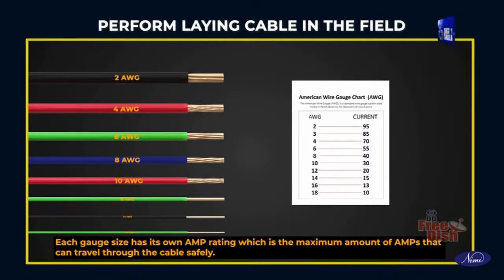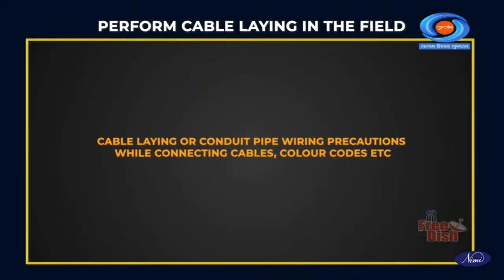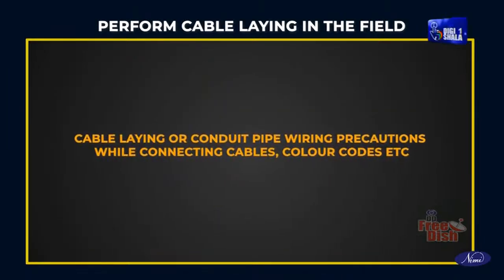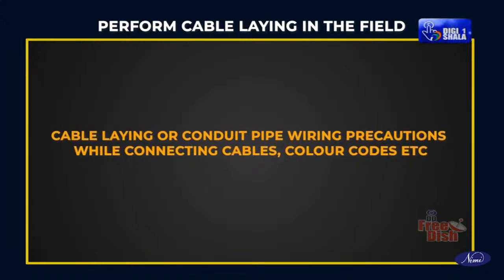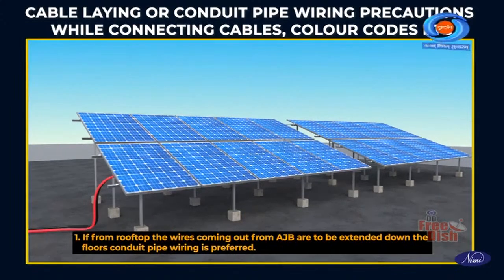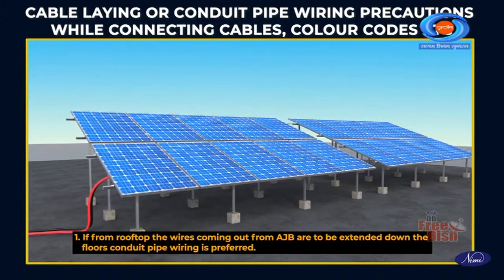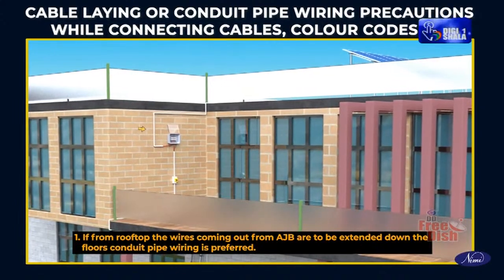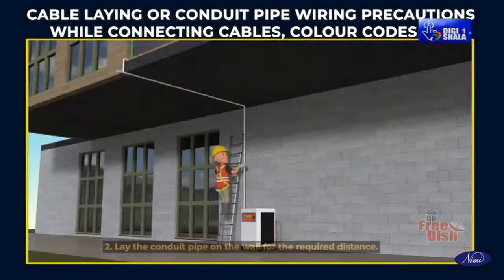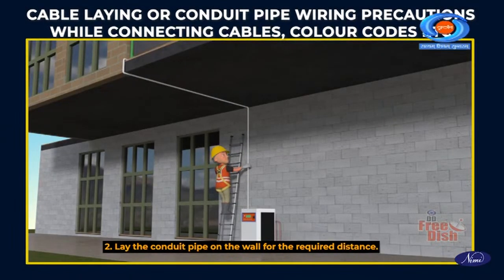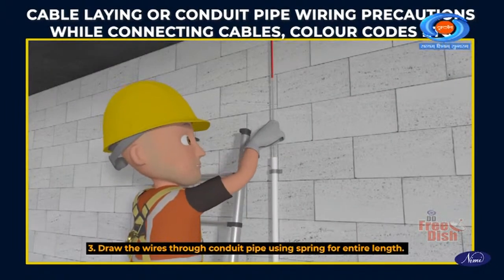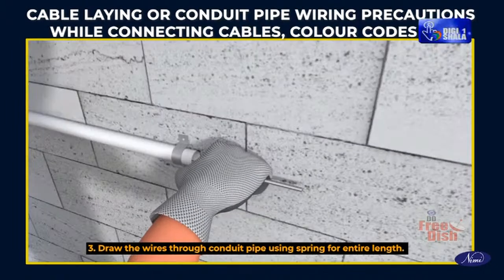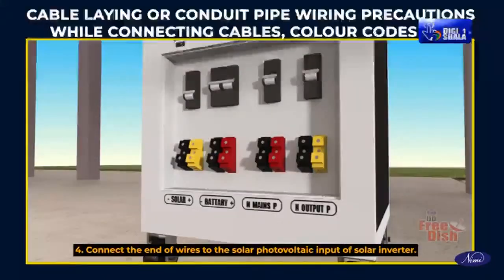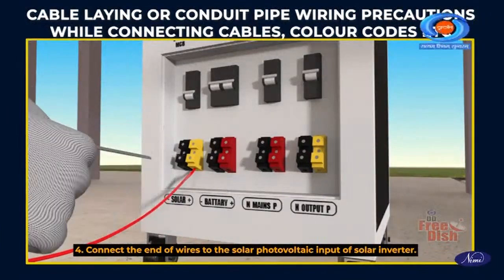Each gauge size has its own amp rating, which is the maximum amount of amps that can travel through the cable safely. Cable laying or conduit pipe wiring. Precautions while connecting cables, color codes, etc. If from the rooftop, the wires coming out from the AJB are to be extended down the floors, conduit pipe wiring is preferred. Lay the conduit pipe on the wall for the required distance. Draw the wirings through the conduit pipe using a spring for the entire length. Connect the end of wires to the solar photovoltaic input of the solar inverter.